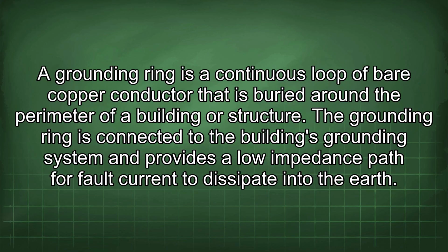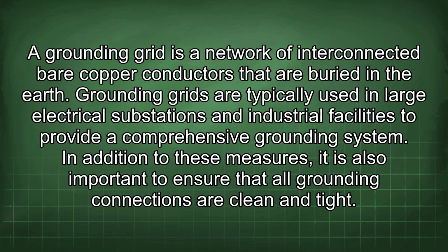A grounding ring is a continuous loop of bare copper conductor that is buried around the perimeter of a building or structure. The grounding ring is connected to the building's grounding system and provides a low impedance path for fault current to dissipate into the earth. A grounding grid is a network of interconnected bare copper conductors that are buried in the earth. Grounding grids are typically used in large electrical substations and industrial facilities to provide a comprehensive grounding system.